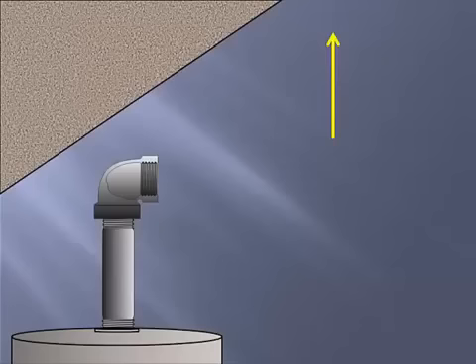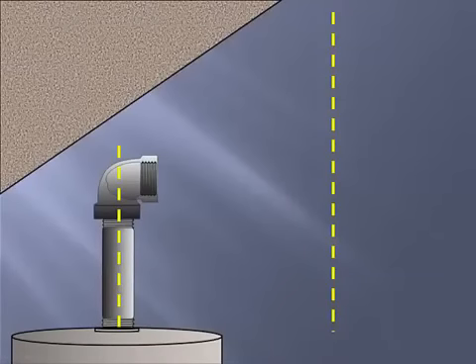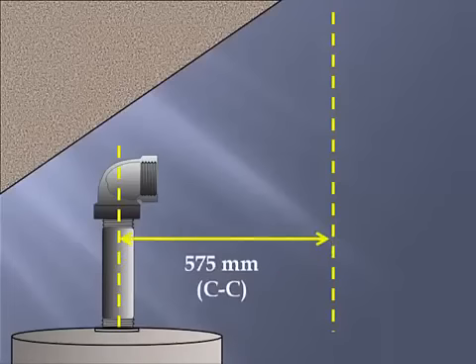First, we're going to establish two vertical lines to take a center to center measurement from the first piece of pipe with its fitting to the location of the next fitting. So we take that measurement and we find that the center to center measurement would be 575 millimeters required.